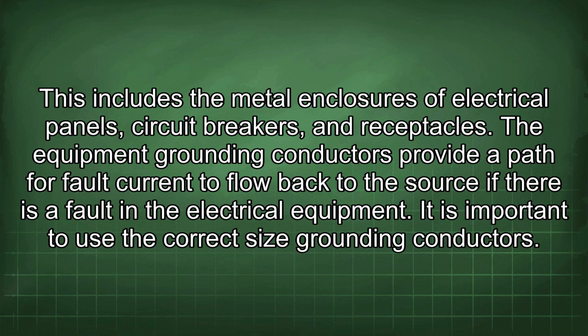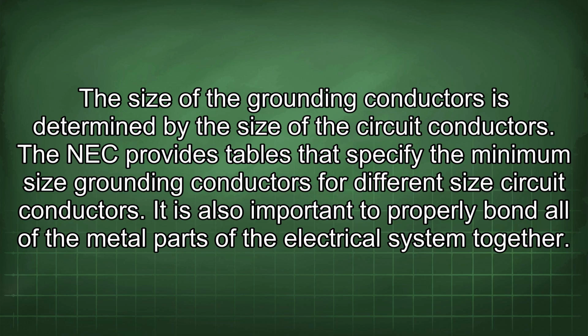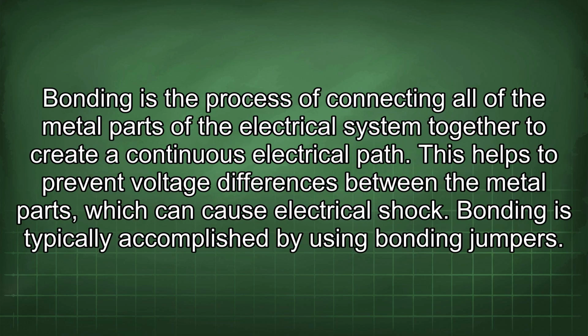It is important to use the correct size grounding conductors. The size of the grounding conductors is determined by the size of the circuit conductors. The NEC provides tables that specify the minimum size grounding conductors for different size circuit conductors. It is also important to properly bond all of the metal parts of the electrical system together. Bonding is the process of connecting all of the metal parts of the electrical system together to create a continuous electrical path. This helps to prevent voltage differences between the metal parts, which can cause electrical shock.